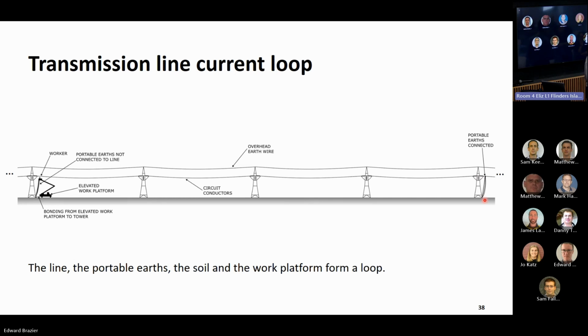It turns out that the isolated circuit conductors, the portable earths off in the distance, the earth return path through the soil, and the path through the elevated work platform, which is bonded to earth through the foot of the tower, and the worker, all form a loop. There's just an open point in the loop from the worker's head up to the circuit conductors above them.